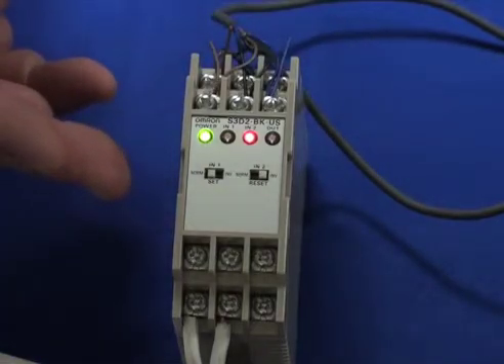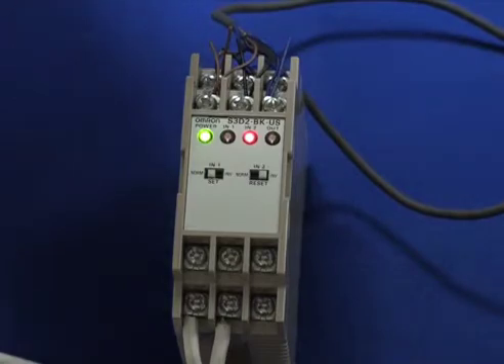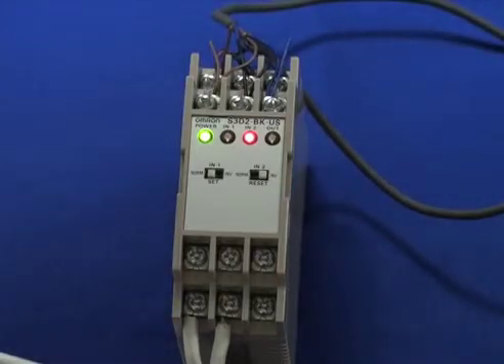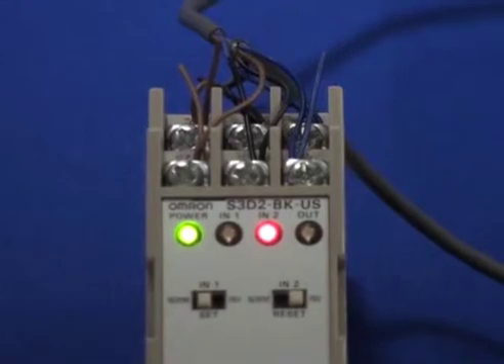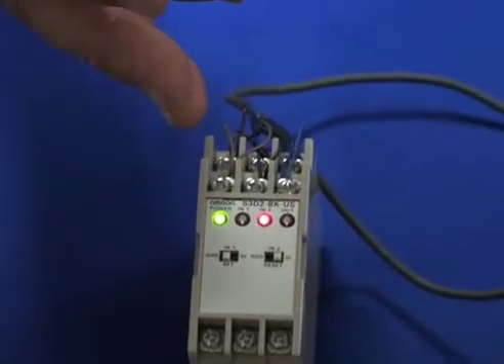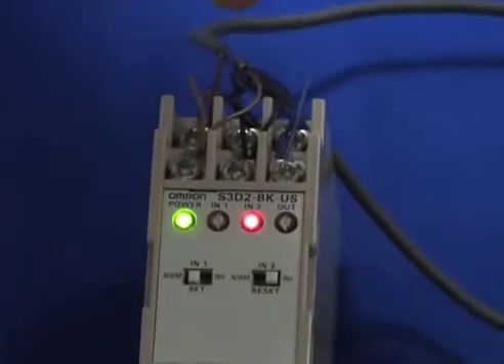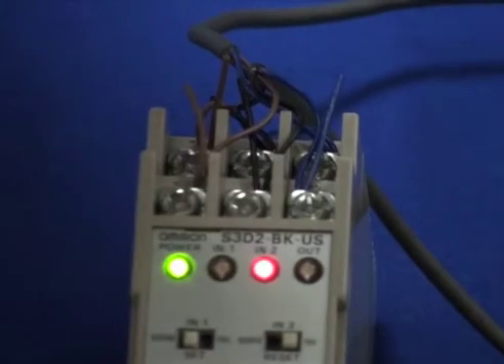In this particular version, the S3D2-BK requires the use of two sensor inputs. In this case we have two NPN style output proximity sensors wired into this unit, and this only operates with NPN style sensor inputs. You simply connect your black, your blue, and your brown wires accordingly to your plus, your minus, and your input.